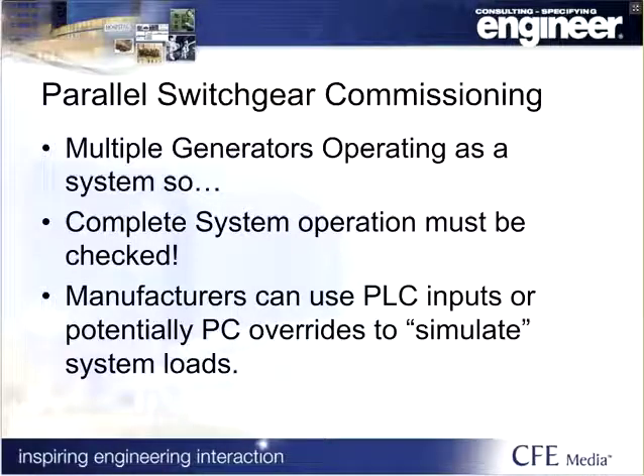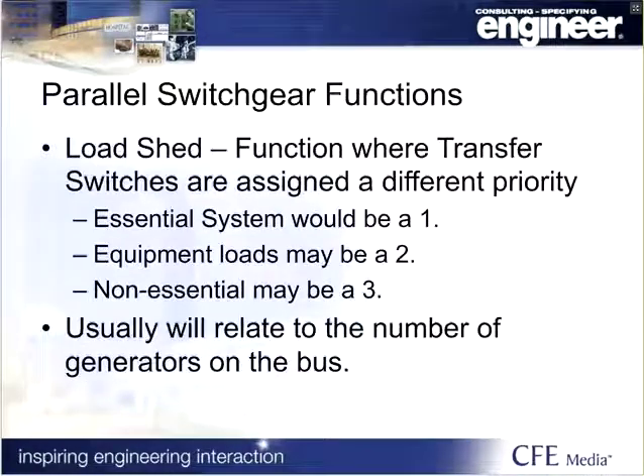Okay, parallel systems. Parallel systems can get extremely complicated, and the load shedding and generator demand response operate and go on and off depending upon what the operating load of the system is. Maybe they'll turn off a generator if you have 6 generators and maybe only need 4 running. They might shut off a generator. So it's pretty in-depth and pretty complicated.